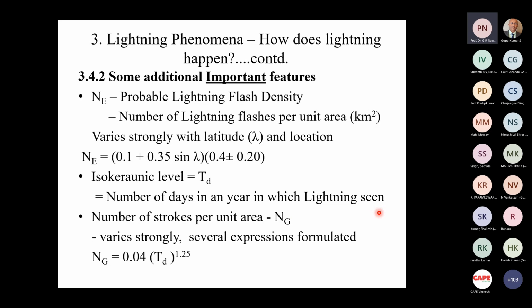The number of strokes per unit area, let's call it Ng, is related to the isokeraunic level by an empirical relationship. Please remember, these are all empirical relationships obtained by observing the phenomenon over many years, probably 20 to 30 years, so there's statistical variation associated with it. Ng, the ground flash density, meaning the number of lightning strikes per unit area per year, is 0.04 multiplied by Td, the isokeraunic level defined above, raised to the power of 1.25.